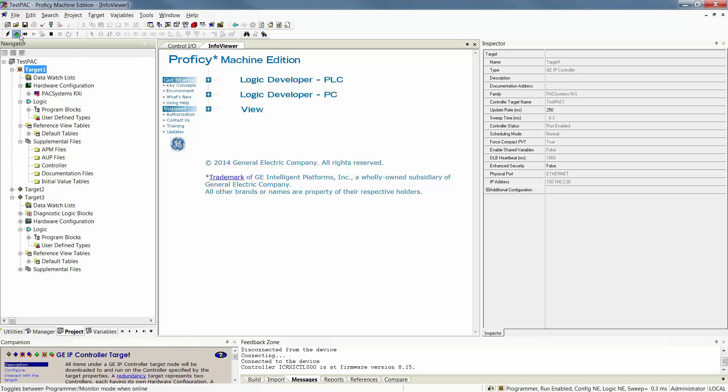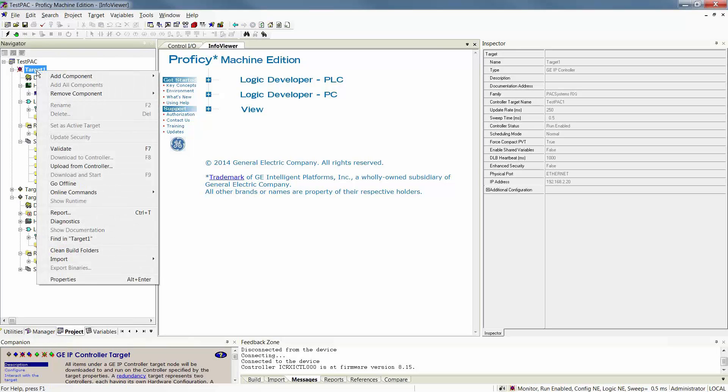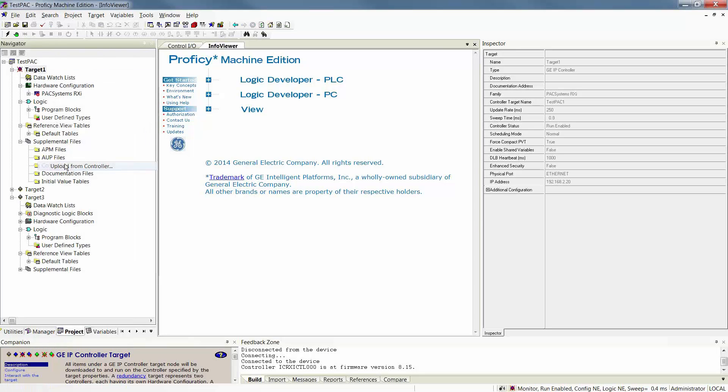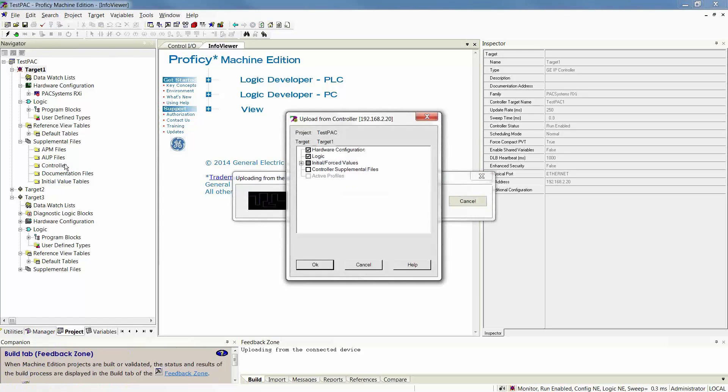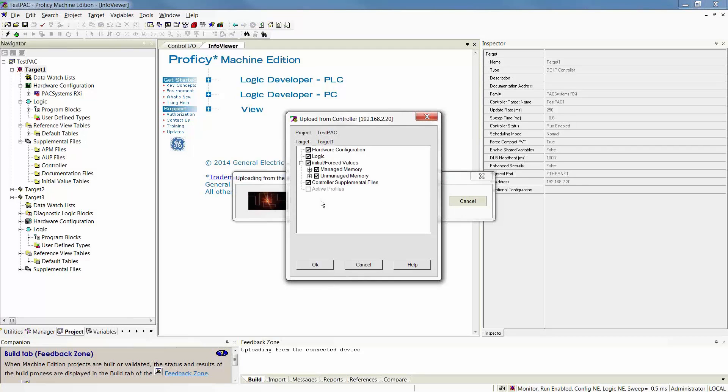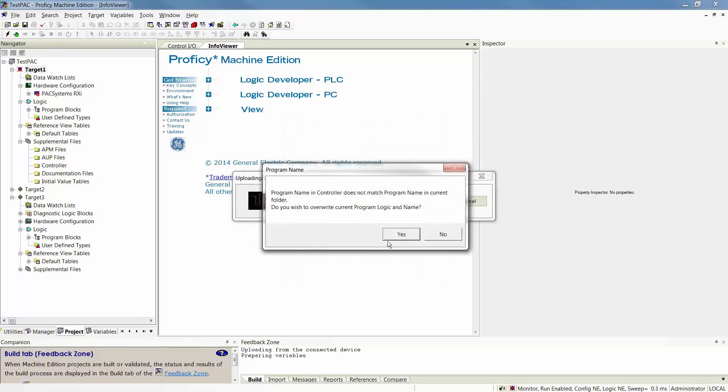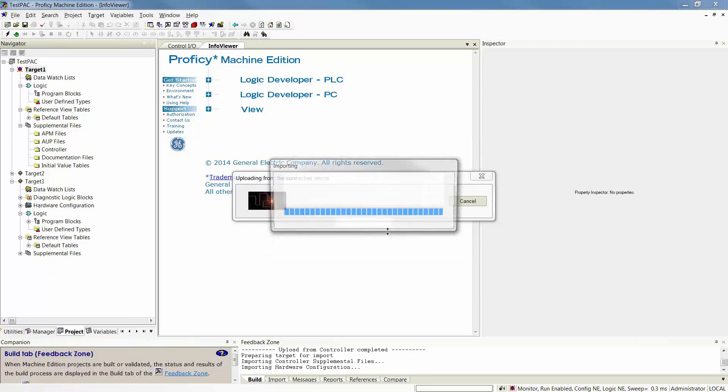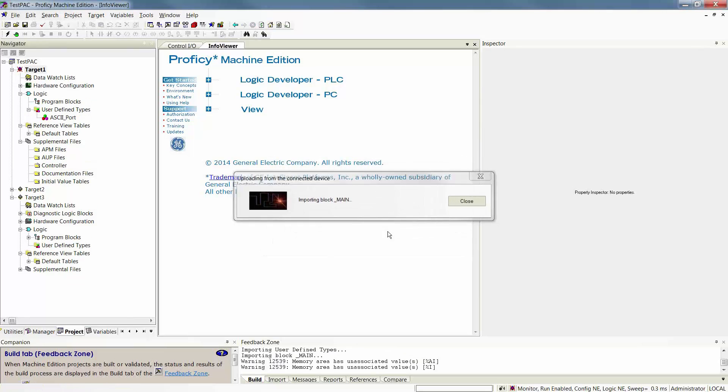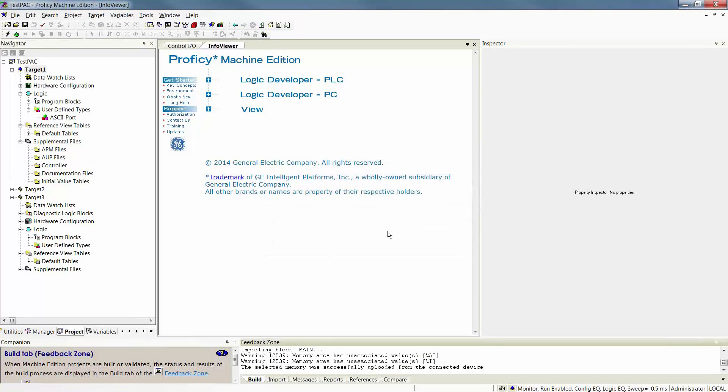If you want to perform an upload to make your configuration or logic equal or both, you simply can actually be in the Monitor Mode. You do not have to be in Programmer Mode. You right-click and upload from the controller. You can upload as many items as you wish, all or nothing. It will warn you if the program names don't match. And as soon as you match, your red X will go away. You'll also see the configuration and logic are equal.